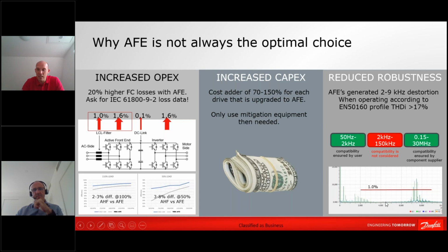So here you might hit a little, but it's so little that you will not see any noise from the bell. As soon as you start having these peaks, that's where you start hitting so hard that you will see the noise coming out of the bell. Or said in other terms, this is where you start exciting harmonics on your power supply. And that is exciting other equipment. That could be a power bank, it could be a drive, it could be other equipment that is vulnerable towards frequencies that are injected here.